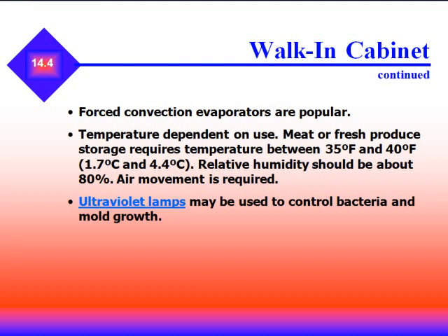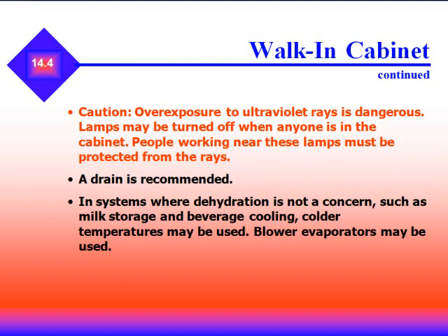Ultraviolet lights can be used to control bacteria and mold growth in walk-in cabinets. Be very careful working around ultraviolet light because overexposure to UV rays is dangerous. Lamps should be turned off when anyone is in the cabinet, and people working near the lamps must be protected from the rays. Walk-in cabinets should have a drain to get rid of any moisture or condensate. In systems where dehydration is not a concern, such as milk storage or beverage cooling, colder temperatures can be used and blower evaporators may also be used.